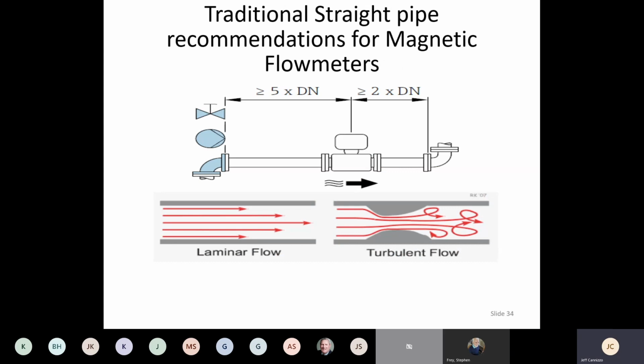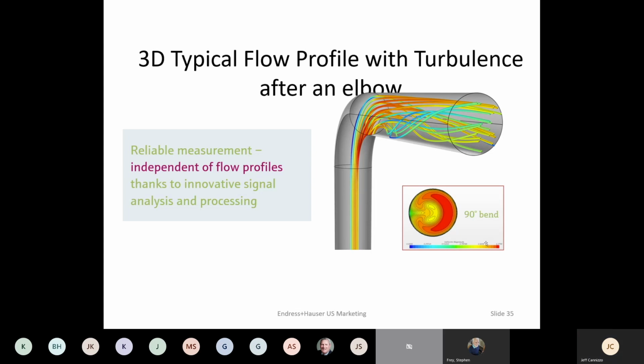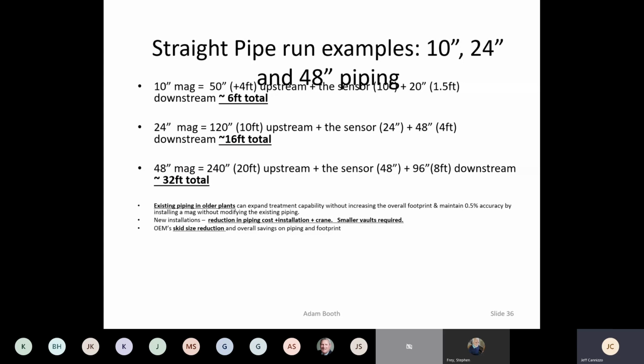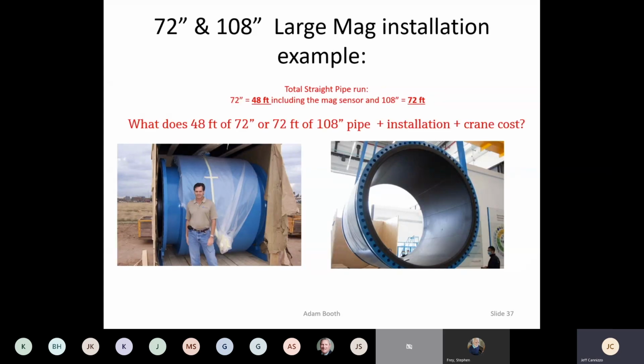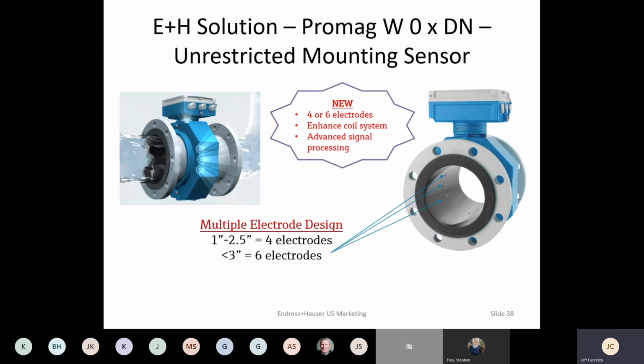So typically with straight run with magnetic flow meters, we wanted 5 diameters upstream and 2 diameters downstream at least. So you can see what happens to the flow profile after an elbow, and this is in all situations, not just water. So if you had a 10-inch meter, you need about 6 feet of pipe. 24-inch needs 16 feet of pipe. 48-inch meter needs 32 feet of piping to meet the accuracy specification. And if you had a real big application, I don't know if there's any water, wastewater people on, 72-inch meter needs 48 feet, and a 108-inch meter needs 72 feet of straight run to get the accuracy specification.